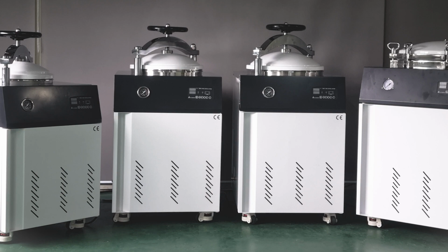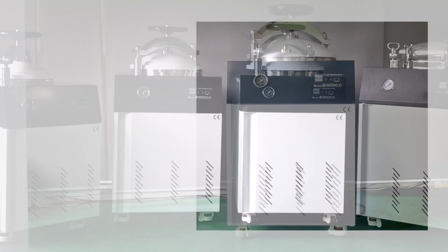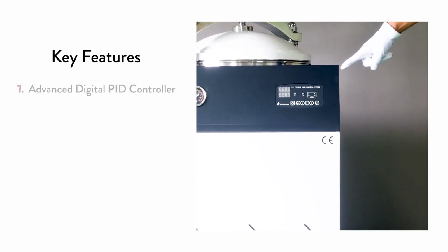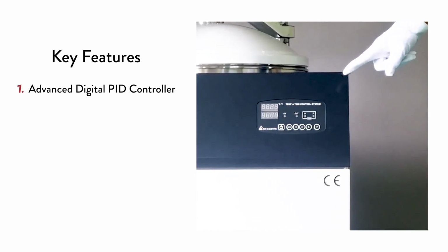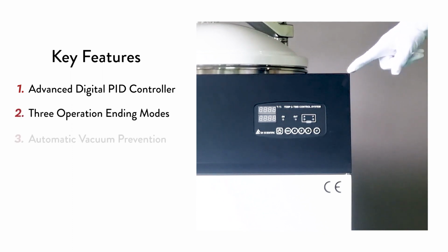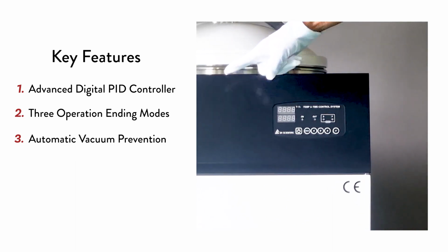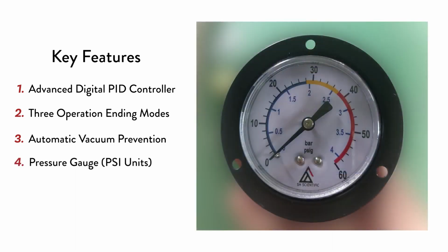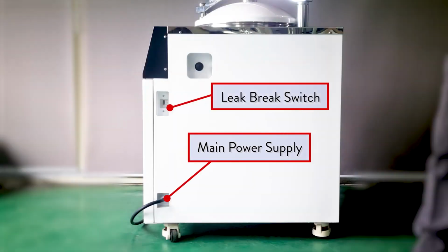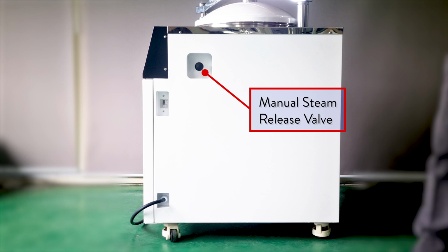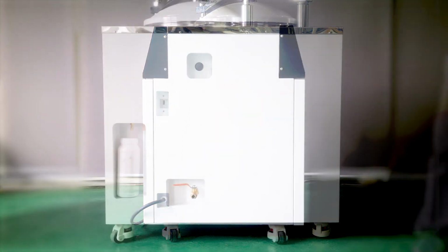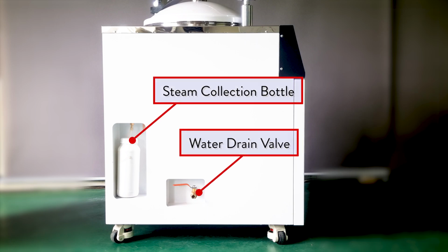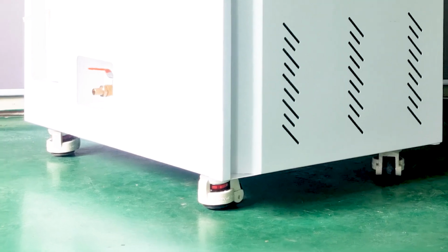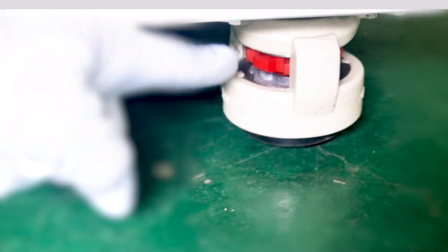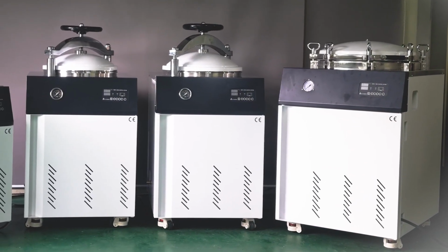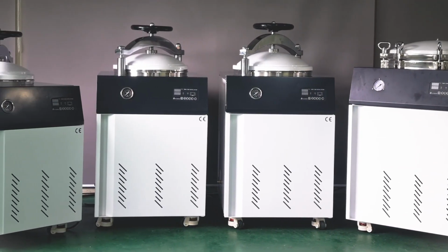Our autoclaves are full of modern, technical features for ease of use. For instance, they're equipped with an advanced digital PID controller for time and temperature settings, 3 different operation ending modes, automatic vacuum prevention, a user-friendly pressure gauge with a PSI readout, a main power supply and current leak breaker switch, a manual steam release valve, also known as a pressure normalizing valve, on the right side, a steam collection bottle, and a water drain valve on the left side. Underneath, 4 caster wheels with brakes make it a cinch to install. And position your SH autoclave anywhere with a 220-volt electrical supply.